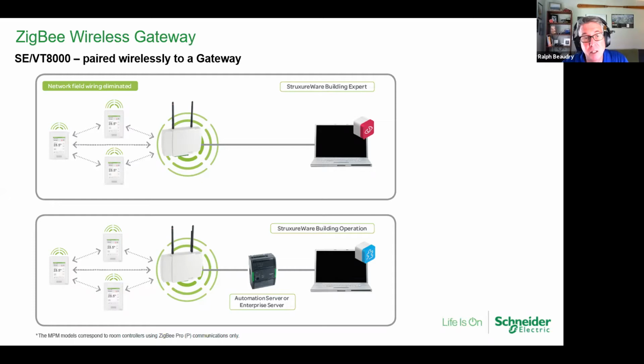You can buy it with just ZigBee on board, or you can buy it with ZigBee and EnOcean on board. Not many people today are using EnOcean wireless, but we do run into projects occasionally. Typically, people use our EnOcean gateway solution as a temperature sensor solution. So it's temperature sensors back in the gateway. Gateway becomes BACnet IP. All the objects are exposed as BACnet objects. We don't sell EnOcean sensors anymore. We used to. We just point you to different manufacturers of EnOcean devices. Today, I'm going to focus on ZigBee, but if you have questions about EnOcean, I'm happy to answer them. So you can buy it with ZigBee on board or ZigBee and EnOcean on board. With ZigBee, I can communicate to an ecosystem of wireless SE8000s.